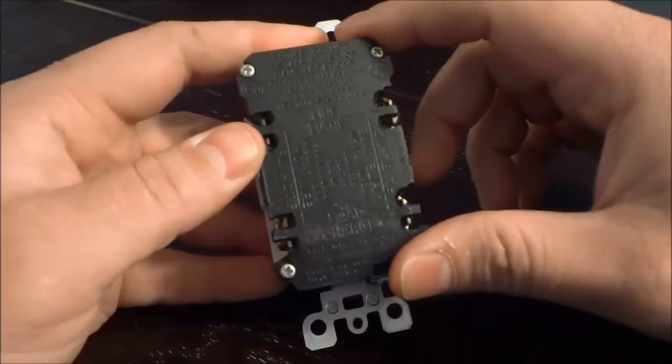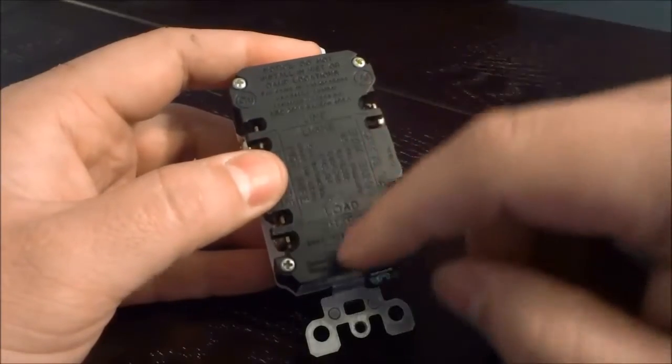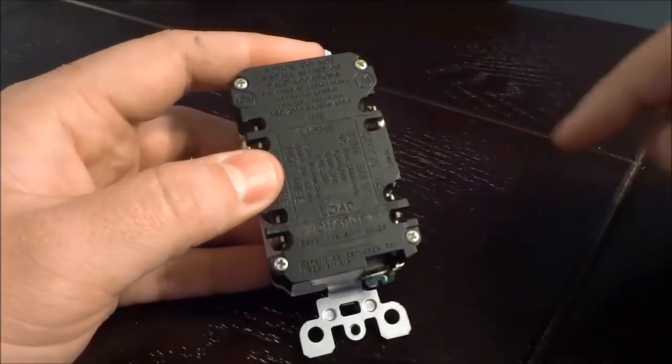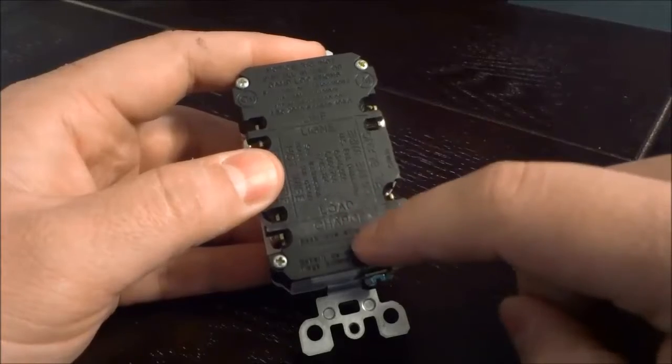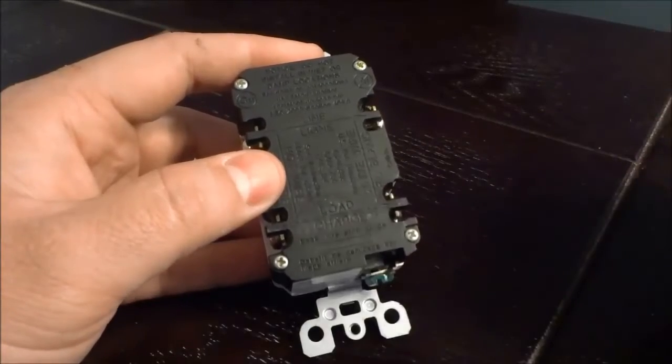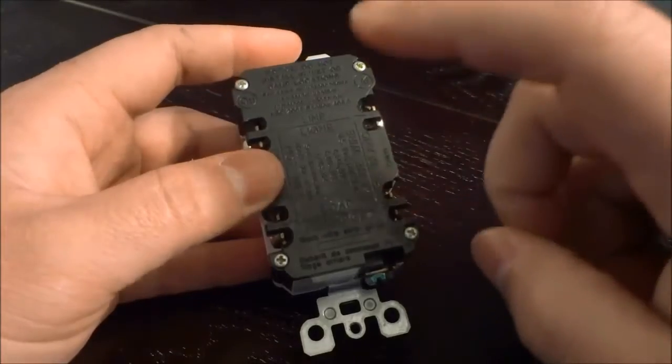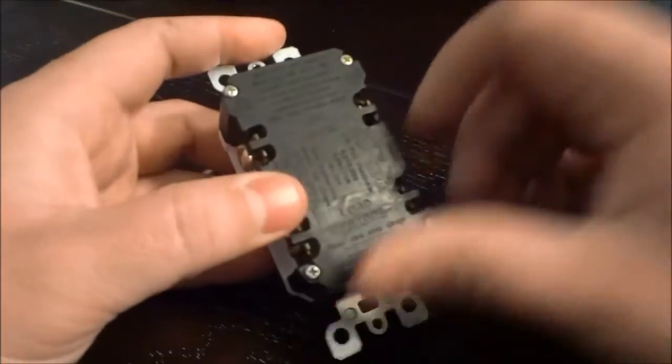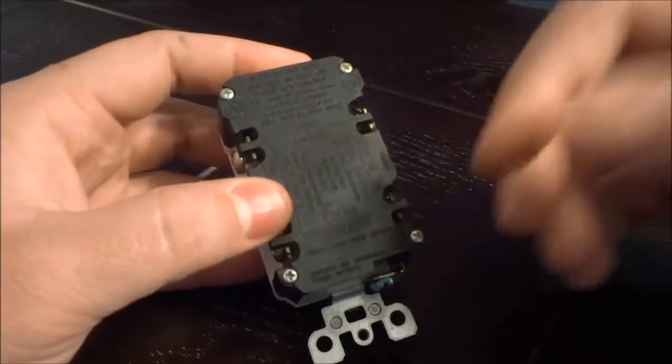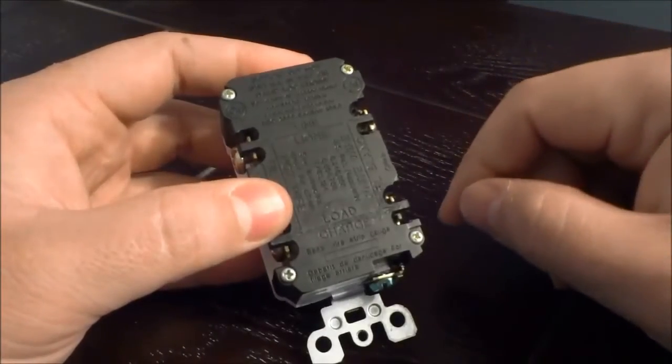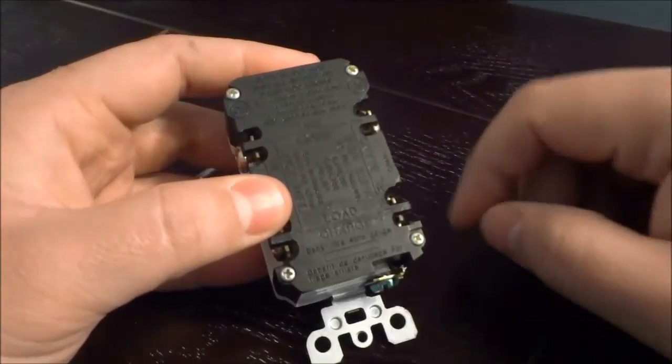The coolest thing about this is that if you are connecting other outlets after the GFCI receptacle on the load side of it, then those additional outlets will be protected in the same way that the GFCI is protected. So that is a really cool feature of GFCI receptacles, and that's basically it.